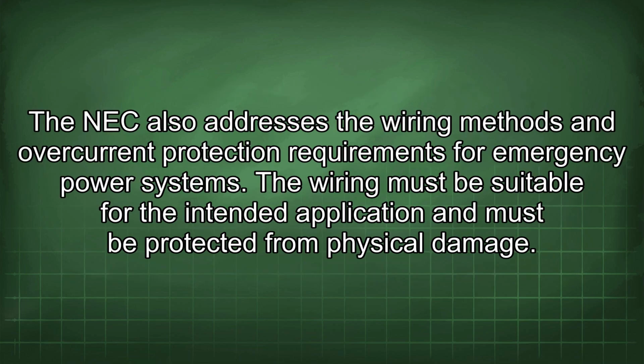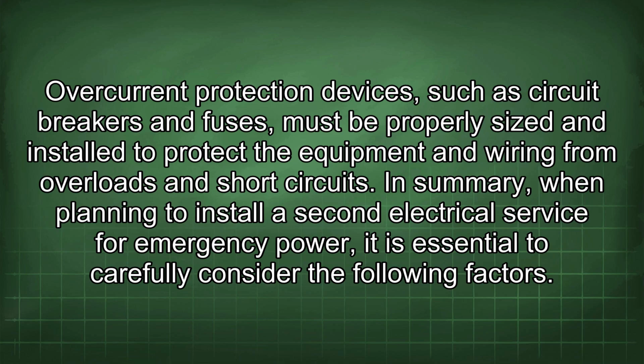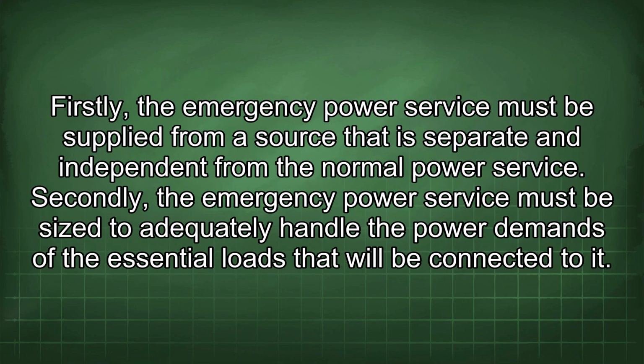The NEC also addresses the wiring methods and overcurrent protection requirements for emergency power systems. The wiring must be suitable for the intended application and must be protected from physical damage. Overcurrent protection devices such as circuit breakers and fuses must be properly sized and installed to protect the equipment and wiring from overloads and short circuits. In summary, when planning to install a second electrical service for emergency power, it is essential to carefully consider the following factors. Firstly, the emergency power service must be supplied from a source that is separate and independent from the normal power service. Secondly, the emergency power service must be sized to adequately handle the power demands of the essential loads that will be connected to it.